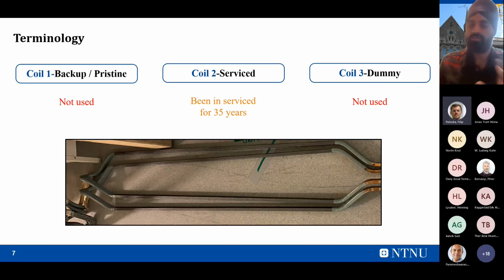And coil 3 is also manufactured, but it's not in use. Basically, coils 1 and 3 are not energized. This one is already energized. But this coil 3, which I'm going to use, is for measurement of the temperature profile around the radial length of the stator bar. So at every 1 meter, I have kept some thermocouple sensors to measure the temperature profile of the insulation, and even drilled holes and put thermocouples inside the copper bars to measure the temperature profile of the copper also.